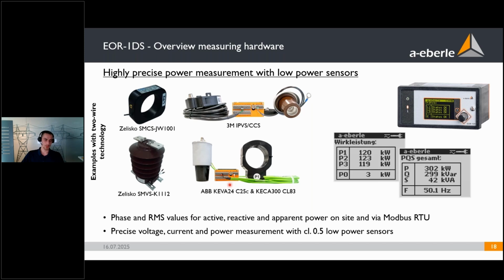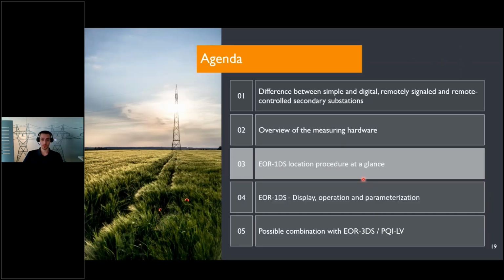This way it's possible to have phase and RMS values for active, reactive, and apparent power on site or transmitted via Modbus RTU, and also precise voltage, current, and power measurement with these class 0.5 low power sensors. So really high measurement accuracy. Which brings us to our next main topic, that is the EOR-1DS location procedure.